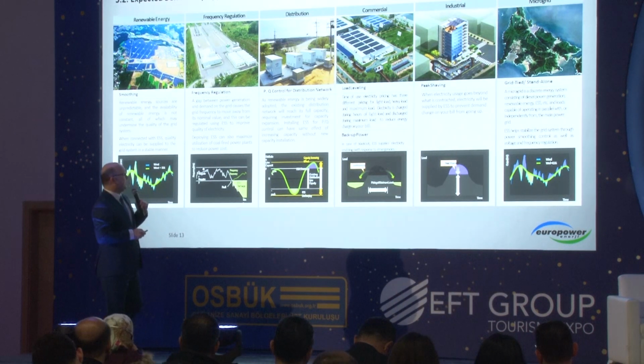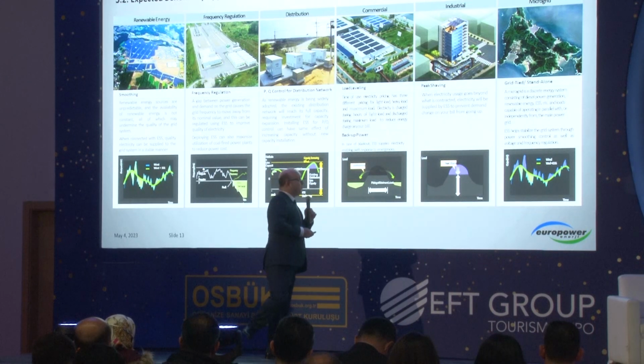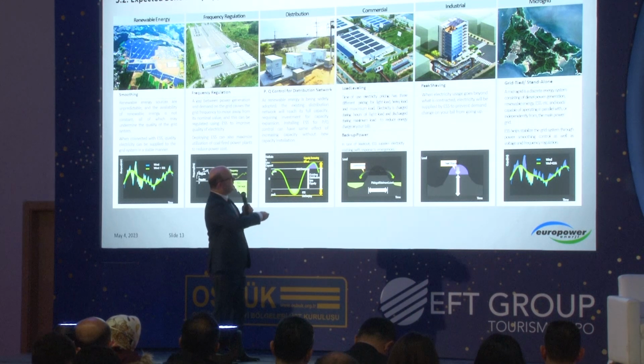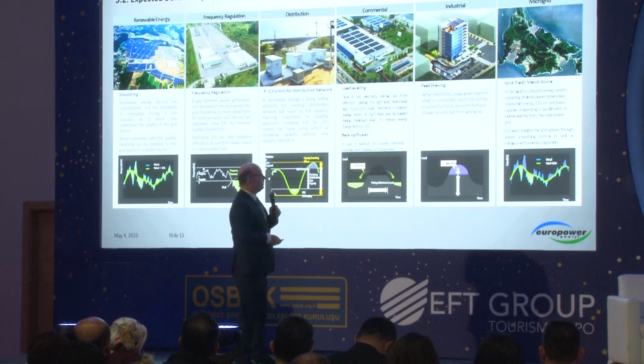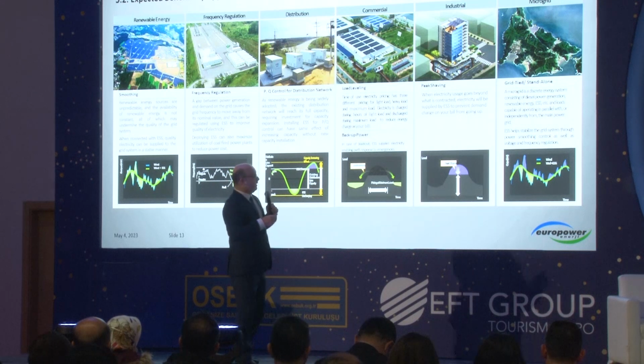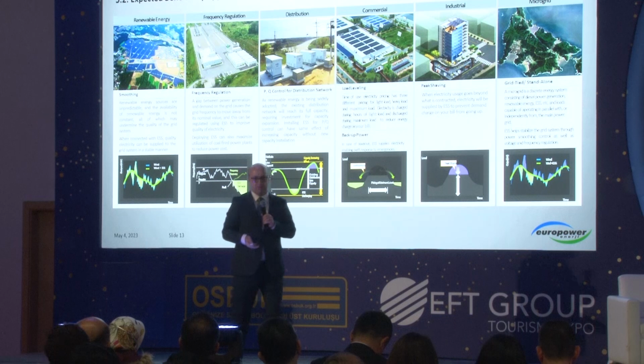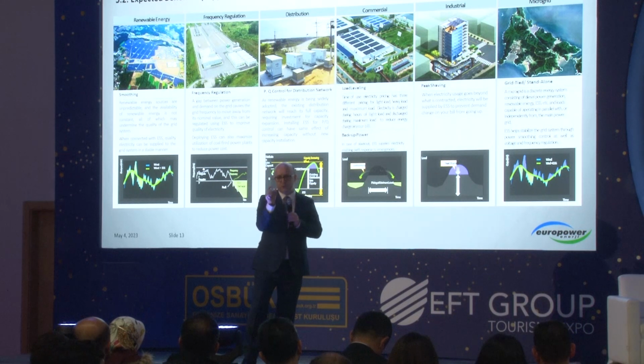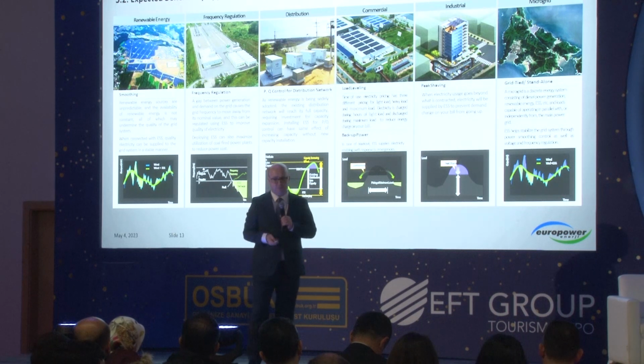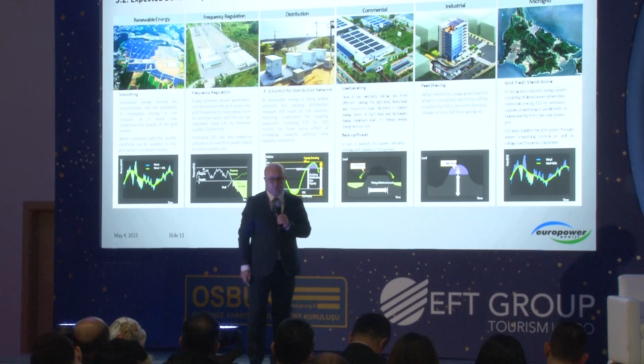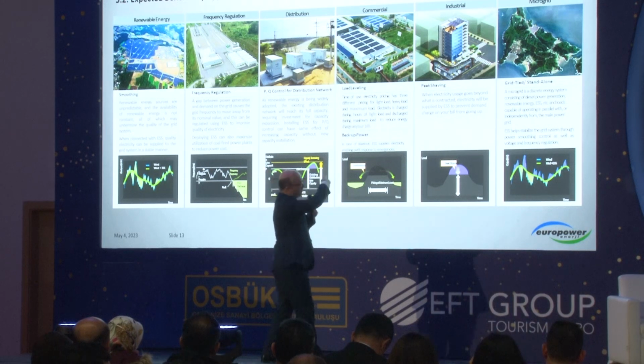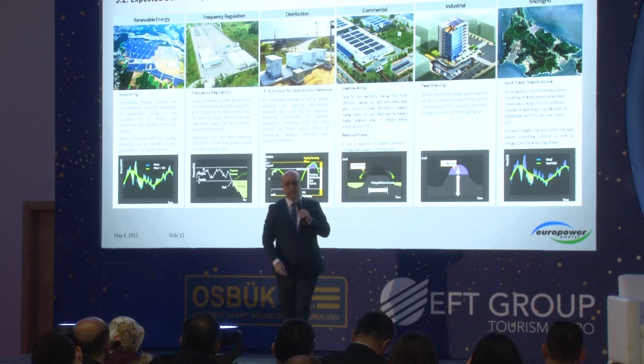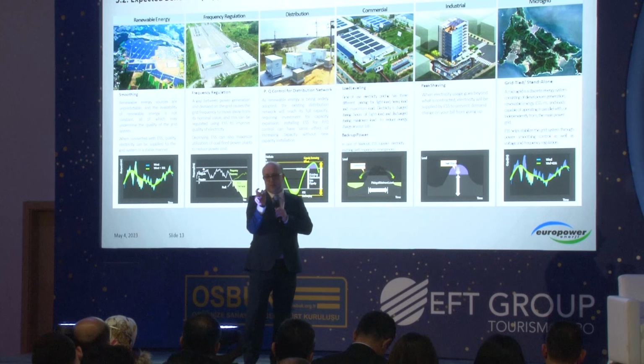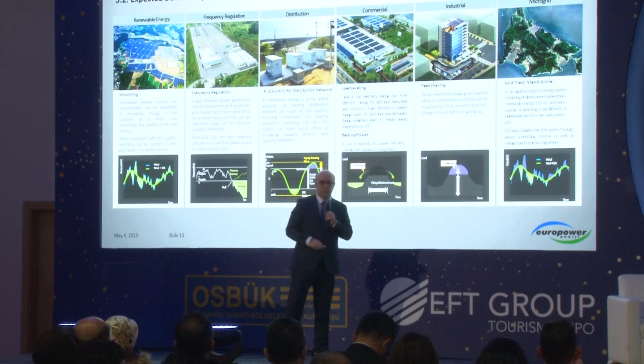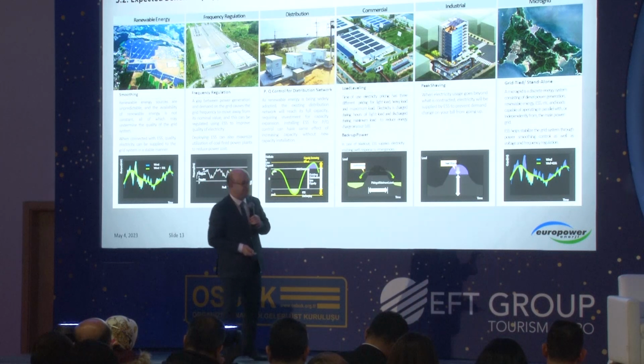And also for peak shaving. Peak shaving is also a very important application that could be executed in industrial settings or even some buildings. For example, you have a demand contract with the electricity distribution company for 10 kilowatt, and for a short while you have to supply 50 kilowatt. What should you do? If you supply this extra power, you will pay a punishment to the distribution company. By using ESS for peak shaving, for the short while that you need to supply higher power than your demand, it will prevent you from having to pay more to the distribution company, the energy seller, let's say.